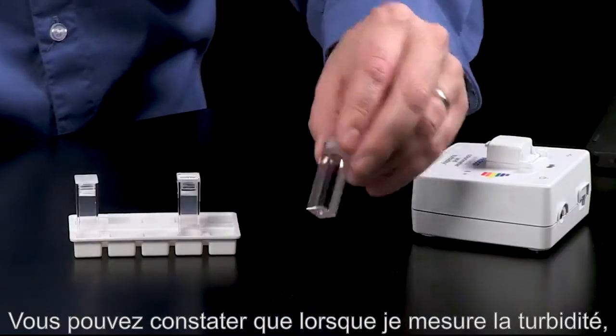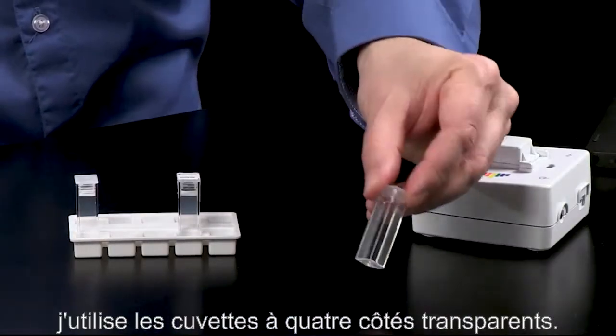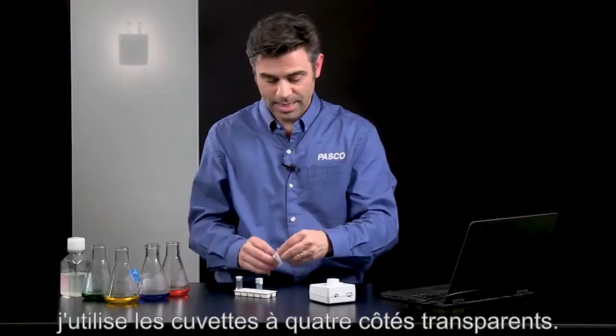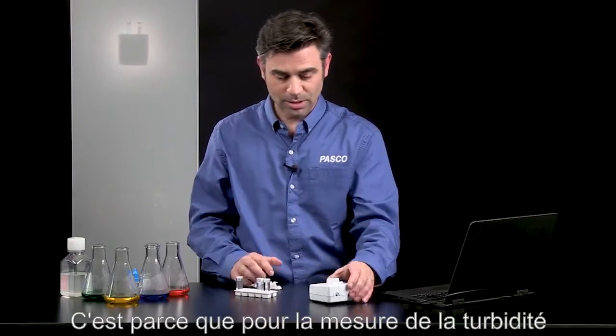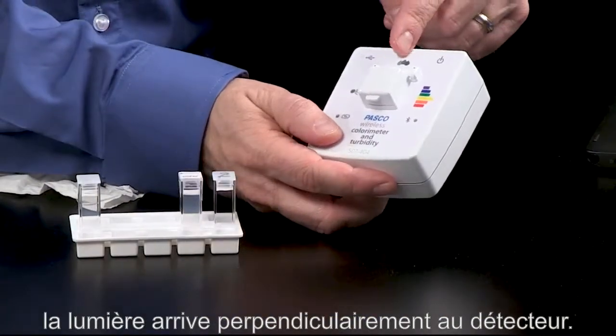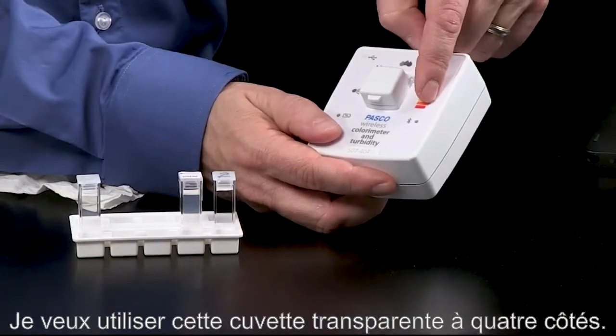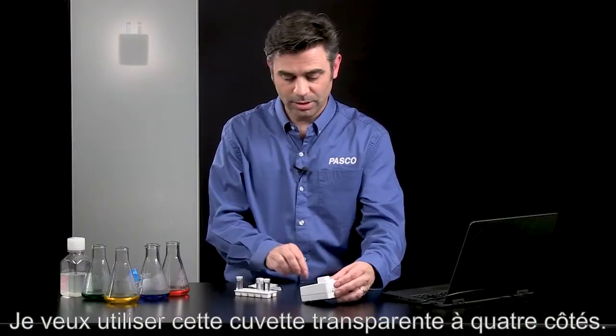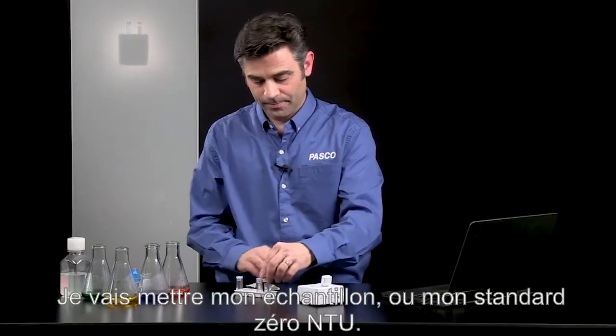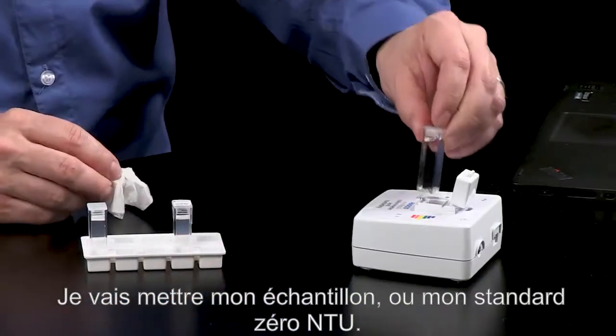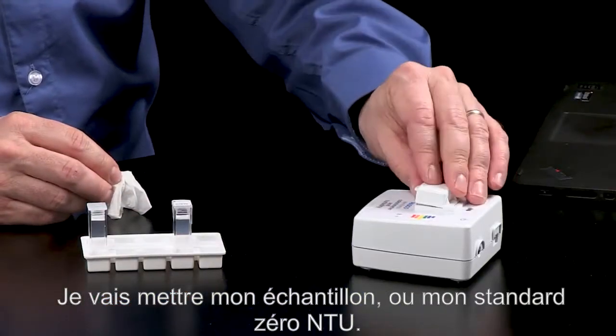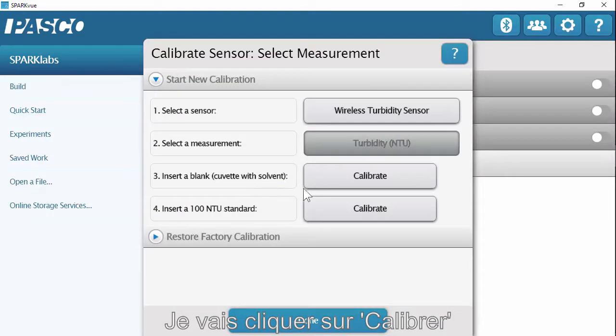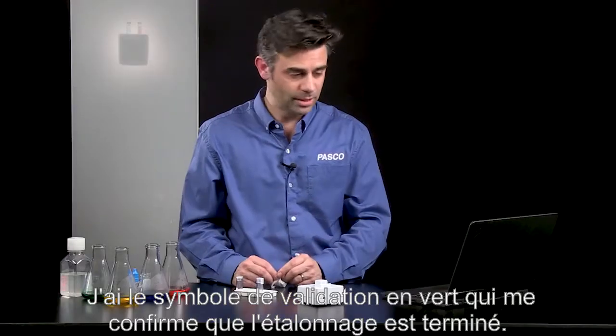So if you notice, when I'm doing turbidity, you want to make sure you're using the 4-sided clear cuvettes. And that is because for turbidity measurements, the light is coming perpendicular to the detector. So I'm going to use this 4-sided clear cuvette. I'm going to put in my blank or my 0 NTU standard. I'm going to hit calibrate. I get that check, so I know that the calibration is complete.